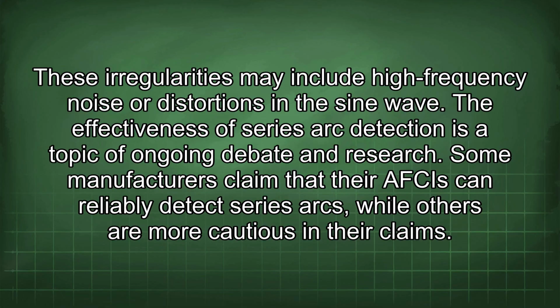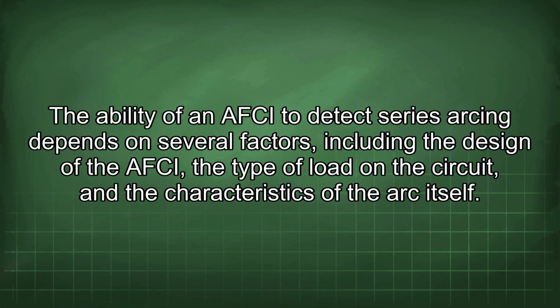The effectiveness of series arc detection is a topic of ongoing debate and research. Some manufacturers claim that their AFCIs can reliably detect series arcs, while others are more cautious in their claims. The ability of an AFCI to detect series arcing depends on several factors, including the design of the AFCI, the type of load in the circuit, and the characteristics of the arc itself.